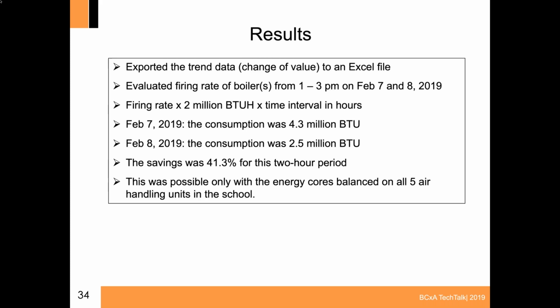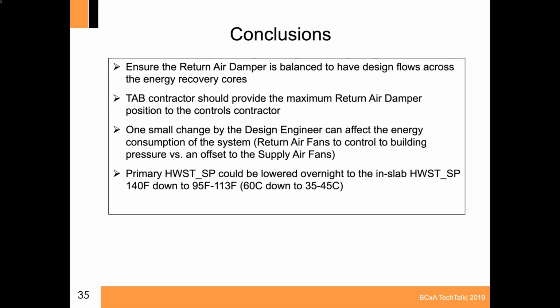And what we found was that on February 7th, the consumption for those 2 hours was 4.3 million BTU, and on February 8th, it was 2.5 million BTU. So the savings from that was just over 40%. And as I said at the beginning, we were a good 20% worse on our gas consumption than predicted. So this definitely was a positive step towards correcting that. One thing we did notice is that this was possible only because we had the cores all balanced. That would allow us to do this, or the school would get too cold. There were no complaints during this period of any zones being too cold.